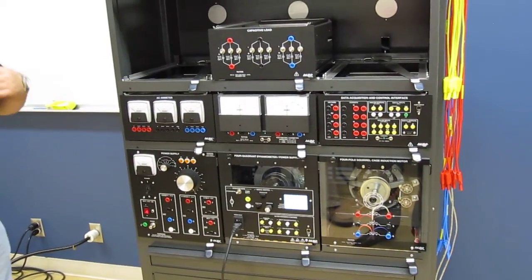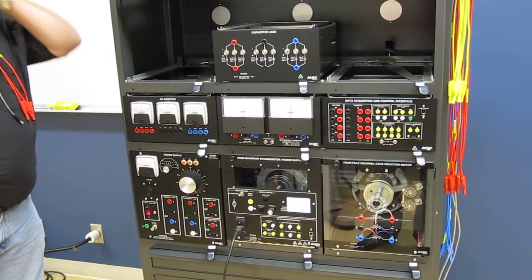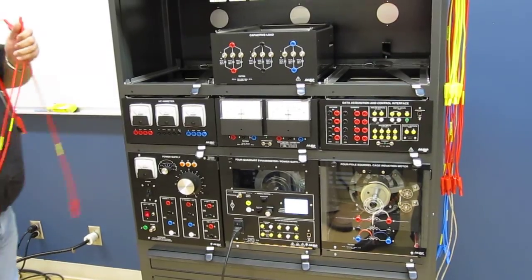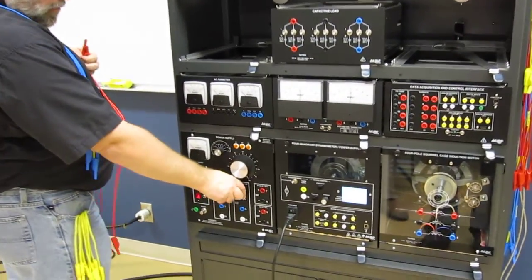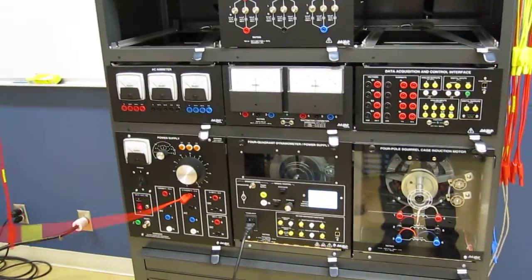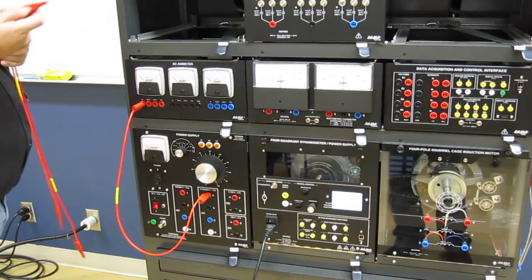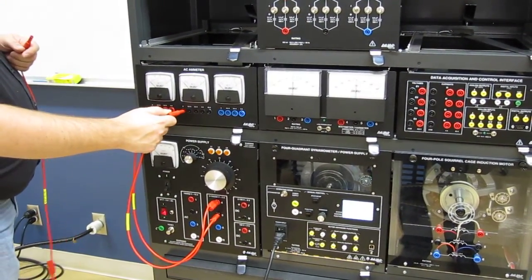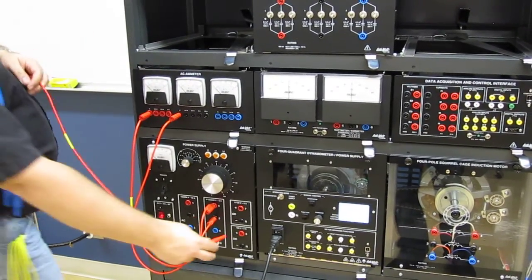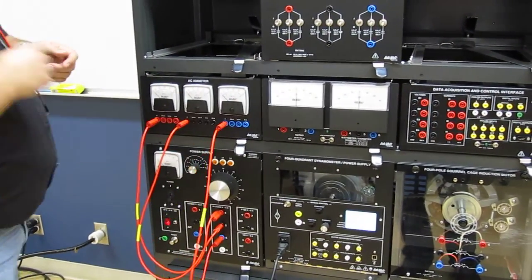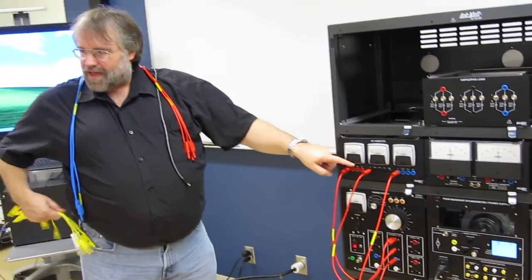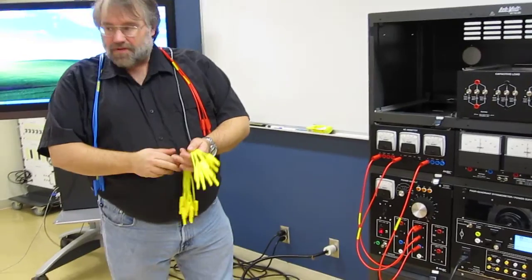First test. After that, what I want to do is monitor the power that is coming out. So I'm taking that from the variable three phase output and putting that through three ammeters. One, two, and three. The logical scale to use in that case would be the 2.5 amps, because I already tested before.